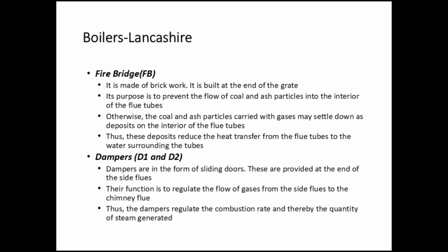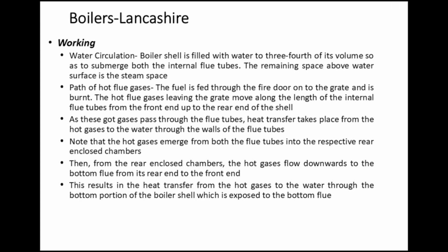Dampers D1 and D2. Dampers are in the form of sliding doors. These are provided at the end of the side flues. Their function is to regulate the flow of gases from the side flues to the chimney flue. Thus, the dampers regulate the combustion rate and thereby the quantity of steam generated.